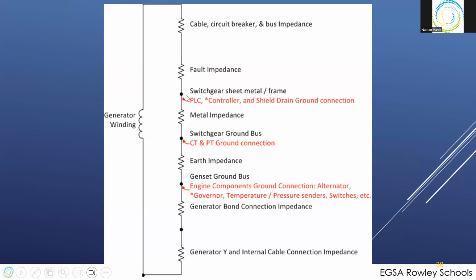It varies with intensity, of course, but there is definitely impedance there. Then it jumps to the switchgear frame and goes down through the sheet metal of the frame. And often the drain wires from PLCs and controllers are connected to the switchgear metal frame, so they might be connected there. There's an impedance in the metal as the current flows down to the ground impedance, to the genset ground bus, to the neutral to ground bond connection, back to the Y and back to the center of the generator. So these are all the impedances in this circuit.